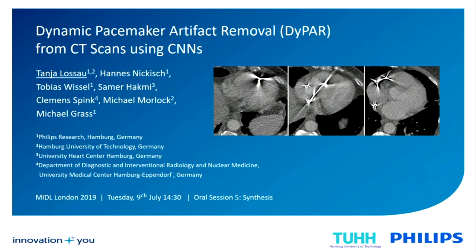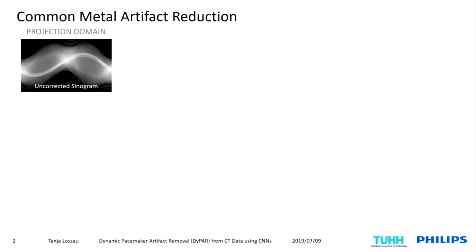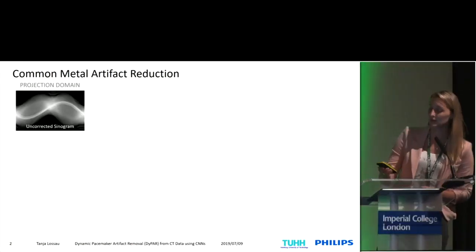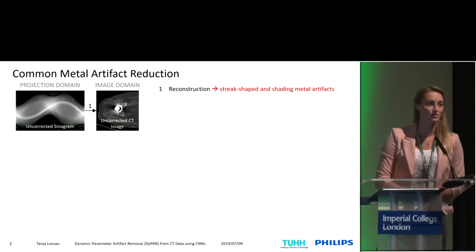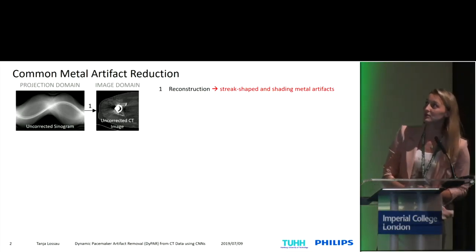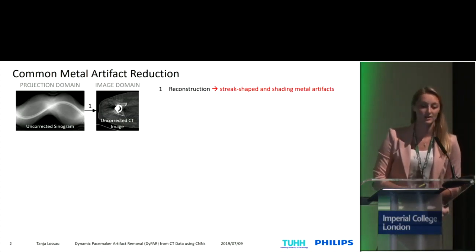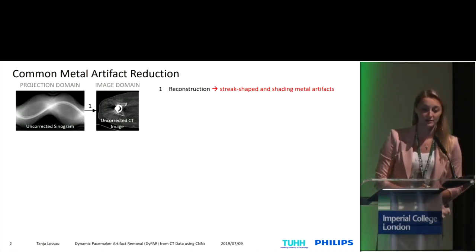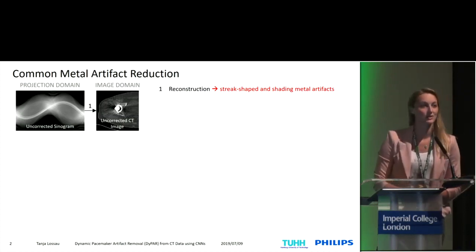Before I start with our approach, which we call DyPAR, let's first have a look at existing typical approaches for metal artifact reduction and why these common methods are not applicable for our case of pacemaker artifact reduction. We will start in the projection domain with the input raw projection data. The first step is a reconstruction of an initial image volume, and you can see these typical streak-shaped and shading artifacts caused by the implanted metal. The neighboring anatomy is not really good visible, which is why we would like to remove such artifacts.